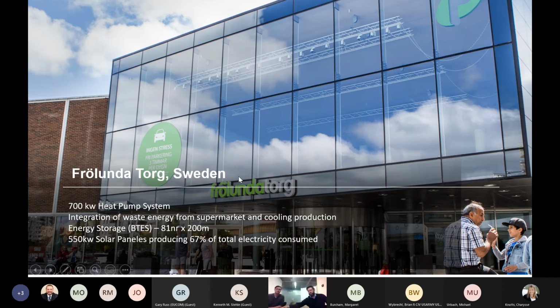Just to give you a more detailed view of something we have actually done: this is a shopping center just outside Göteborg, one of the main cities in Sweden. Here we have done a 700 kilowatt heat pump system, 700 kilowatt heat output. We're integrating with the condenser heat, the reject heat from the supermarket cooling production, as well as the comfort cooling in the shopping center.